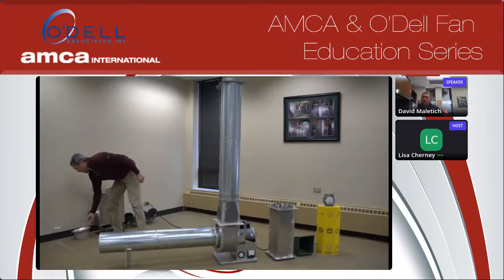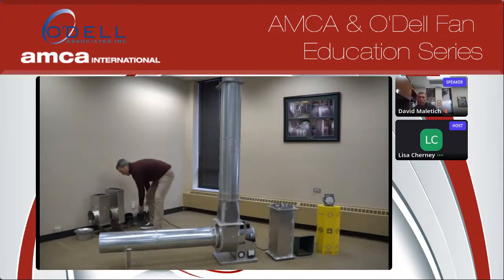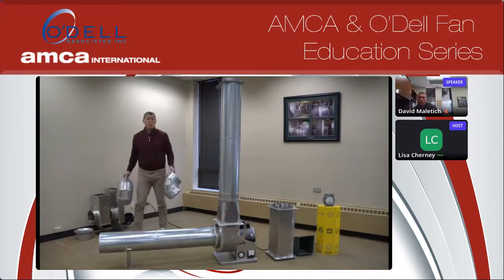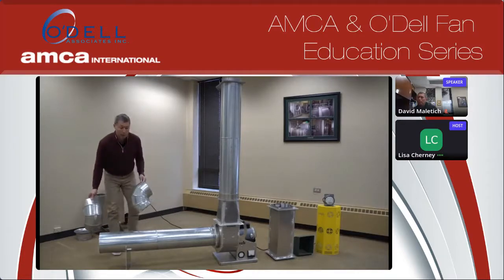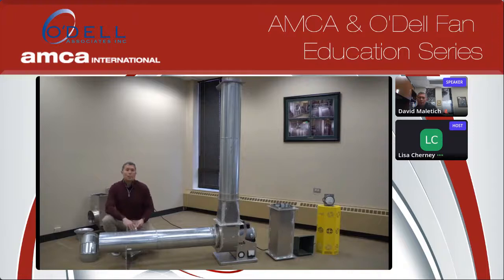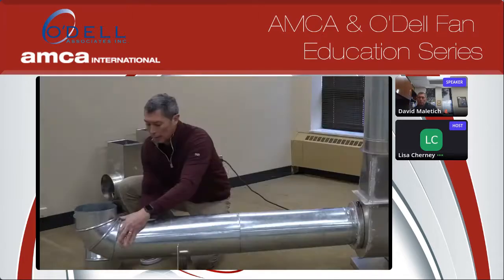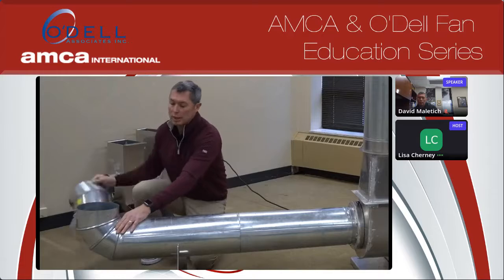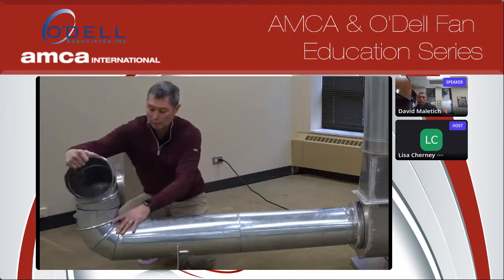And the problem with corkscrews is that corkscrews can go down a piece of ductwork for an extended period of time. The fan itself wants to create a venturi or a vortex as the wheel rotates, and if we create a vortex over here, that vortex will continue down that straight run of duct.